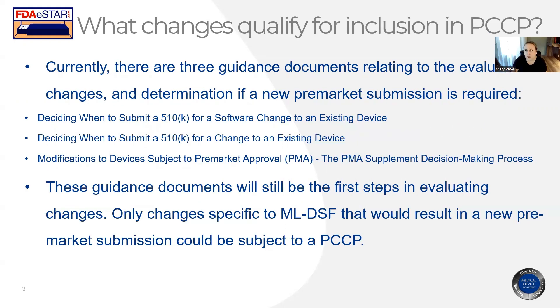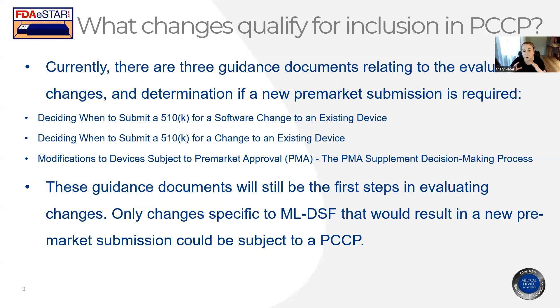What types of changes would qualify to be included in a PCCP? Currently there are three guidance documents that relate to evaluating changes and determining when a new pre-market submission is required. Those three guidance documents would still apply, and anything relating to MLDSF changes that would require a new 510K per those guidance documents would be the subject of the PCCP. Those are still the first steps in evaluating changes, and any changes that would call for a new marketing submission are what you would cover in your PCCP.